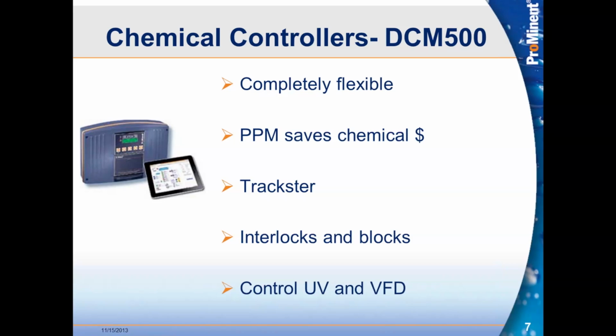So what we can tell the DCM 500 to do is, if it initiates an autofill event, we can tell the controller not to allow any chemicals to feed during that autofill event. And again, we come back to the concept of smart, precise dosing of chemicals, doing things only when they're really needed, and then doing them very precisely and very well. So this is the smart disinfection, the smart control concept that we like to drive home with the ProMinent products.